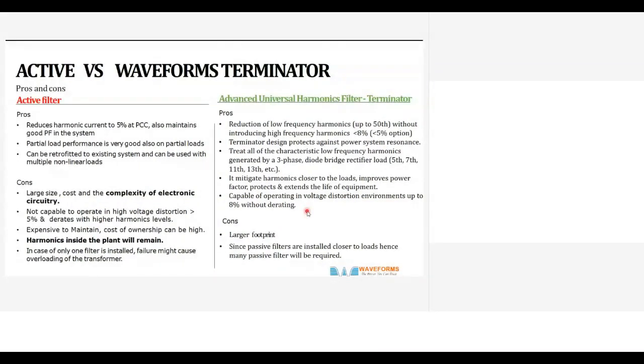So if it is connected to a drive, drive breakdowns can be very infrequent, or it will not cause any breakdowns at all. It will protect the drive. The drives can fail for some other reason, but not due to poor power quality. It's capable of operating in a voltage distortion environment up to 8% without derating. So even if there's voltage distortion at the input, it can still operate comfortably. That's the only problem with this.